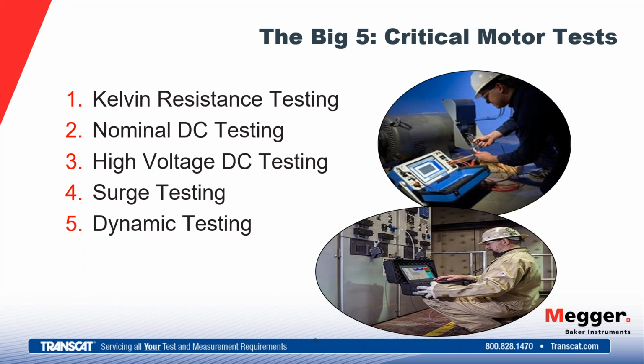The second one is going to be DC testing, a nominal DC testing. So this is again a test performed at or below nameplate value of the motor. And it is looking for our ground wall insulation integrity. So here we're going to evaluate ground wall insulation at or near nameplate voltage.